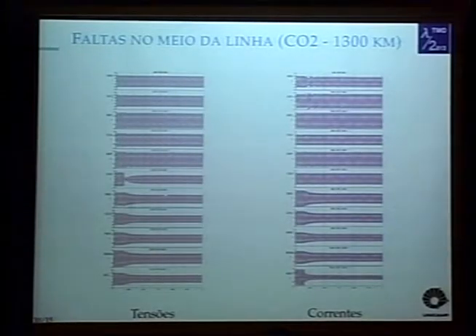Only the voltages in Colinas 2 and the substations forward were in a sub-voltage state. Here we also have the currents. The same thing happens. There are basically no changes in the currents, not even in the Colinas 2 substation where the fault happened. Current is basically the same. Only in the substations ahead did the currents decrease.